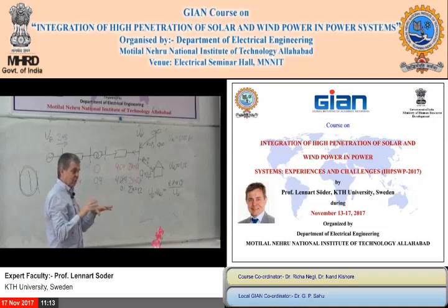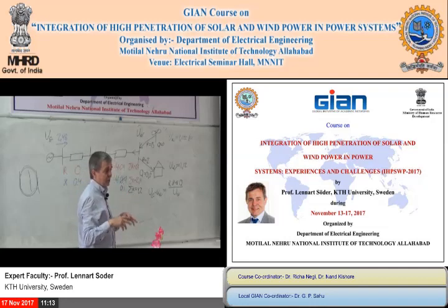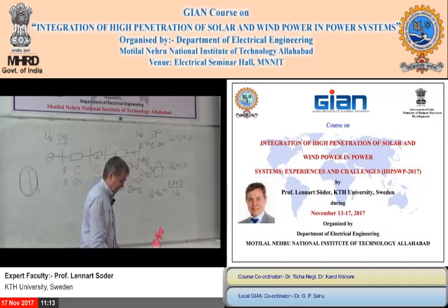I can say that exactly about now, this is a really hot topic. We are discussing internally with companies like ABB and so on. There is a discussion now that the system operators will require inertia from, for example, wind power systems. And then the question is how to make these fundamental calculations. Do we really have synthetic inertia? You have to measure the frequency, but if there is no inertia, there is no frequency to measure. This is really fundamental. Can you have an RMS modeling at all in the system if you don't have an inertia? But then we are coming down to a really small amount of inertia.